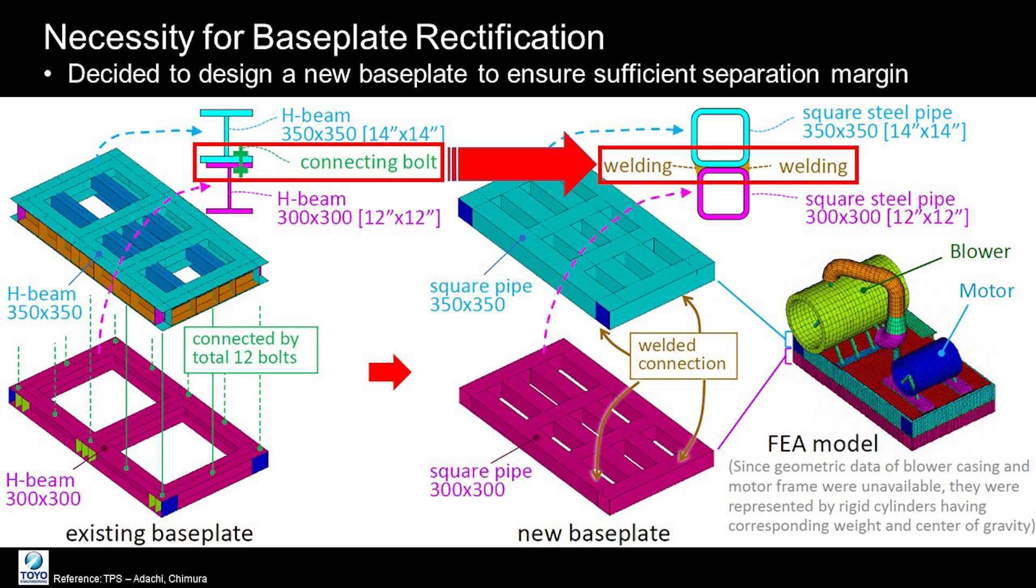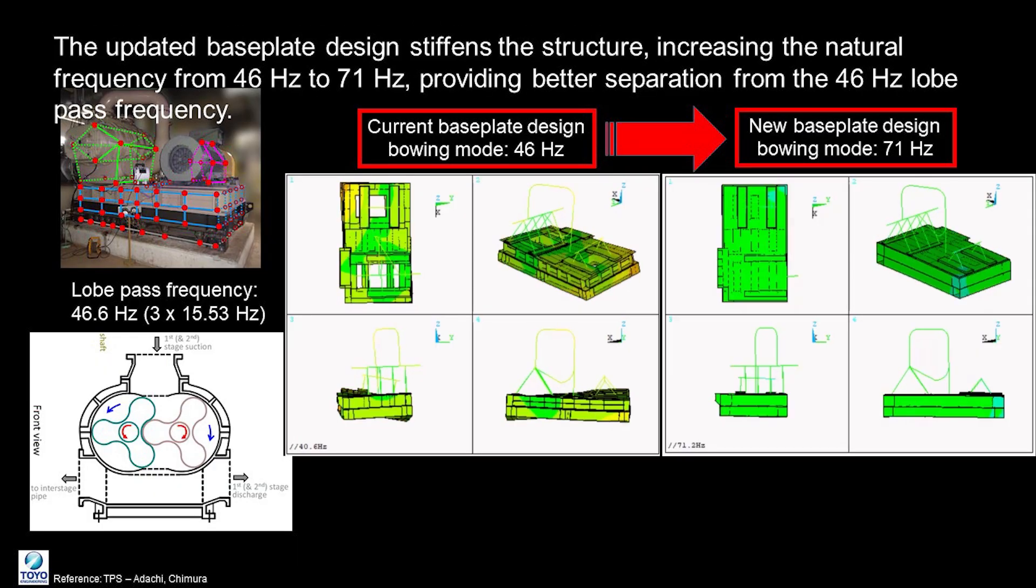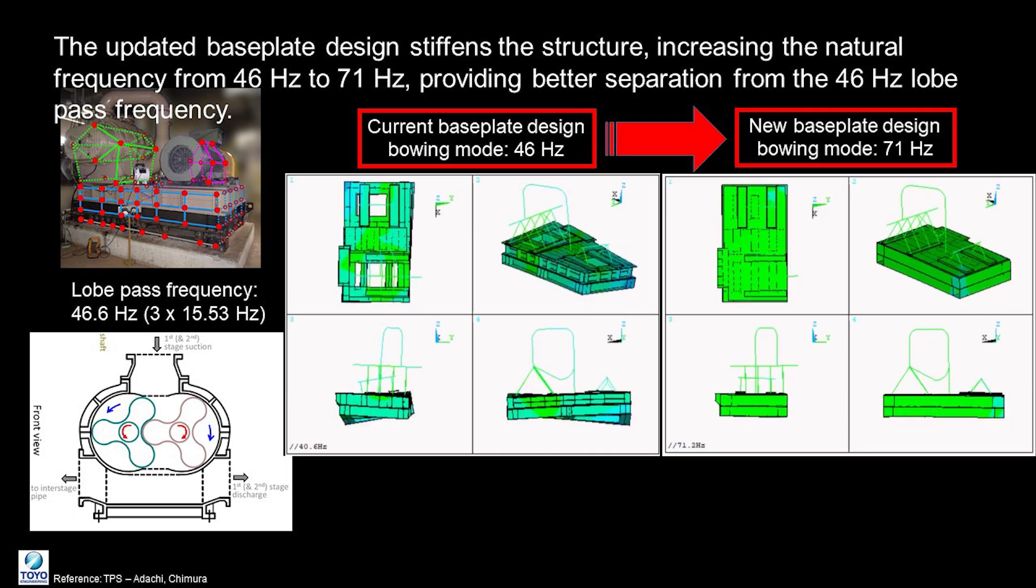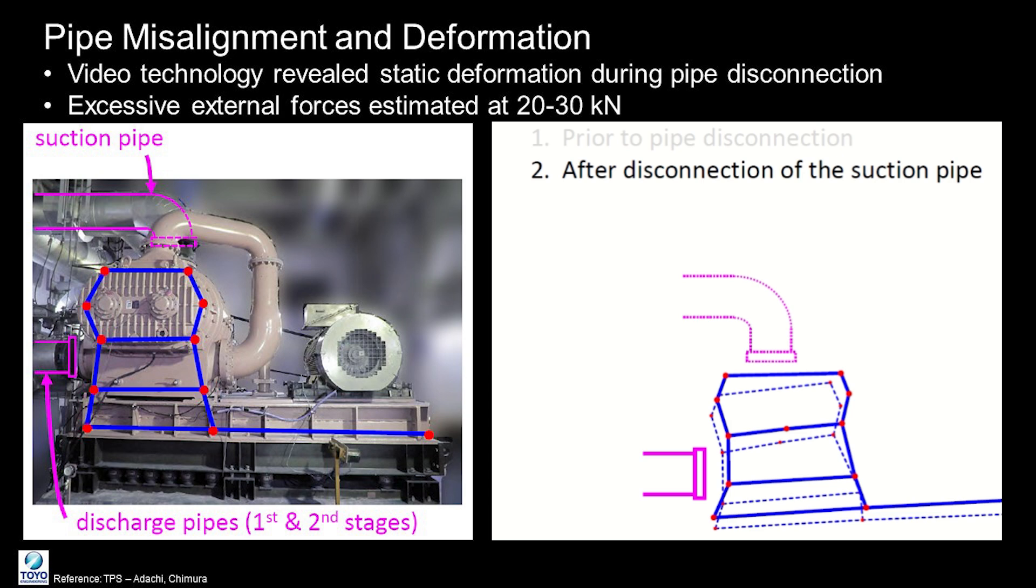It was first considered to stiffen the existing base plate, but it was determined that a completely new base plate design would be more effective. This decision was based on modal analysis and finite element analysis simulation. The updated base plate design stiffened the structure, increasing the natural frequency from 46 Hz to 71 Hz, providing better separation from the 46 Hz lobe passing frequency.